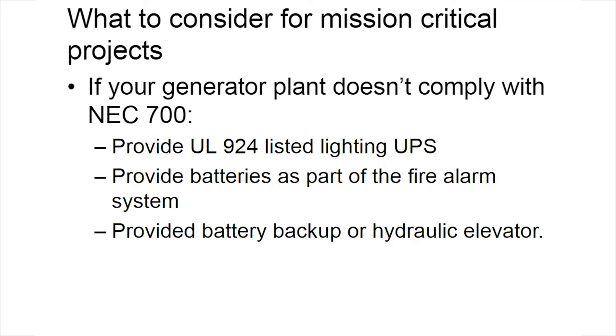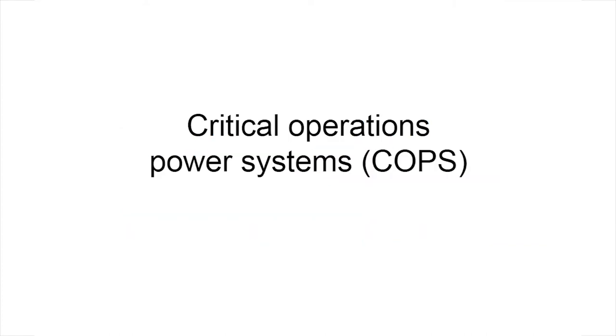Things that you should watch out for if you don't want your plant to comply with 700 on a mission critical job: you should make sure you put in a UL 924 listed UPS. You make sure that you provide batteries for your fire alarm. Make sure that if you have an elevator, it is either hydraulic or has a battery backup on it. There are many elevators out there now where you can provide battery backup as an option. That means you don't need to comply with any of the 700s. It's interesting how we work around this. The concept is not to comply with a section, or not to use that section, or not to make our generators follow that section, which is an interesting thought, a little bit different from what we've seen.